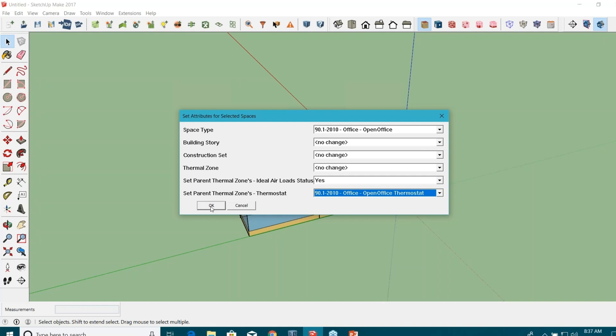Now I have installed the ideal air load status in these spaces. These spaces now have infinite capacity for HVAC systems — heating and cooling — are always available, and have 100% efficiency. The reason you'd install ideal air loads is that a lot of times you just need to do some internal load calculations or space load calculations — what people used to do in Trace or other tools. You don't need to go through all those crazy MEP details. You can just install the ideal air load and it will give you all the information like space loads, and based on that you can size your MEP system.